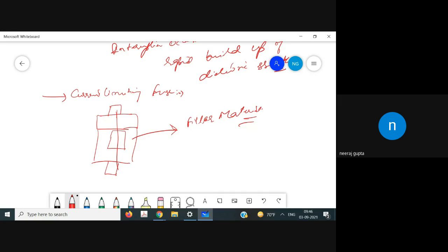Typically, the filler material used in this case is silica sand, to contain the arc as well as to maintain a very high pressure in a long restricted arc area caused by the melting of the full length of the element.